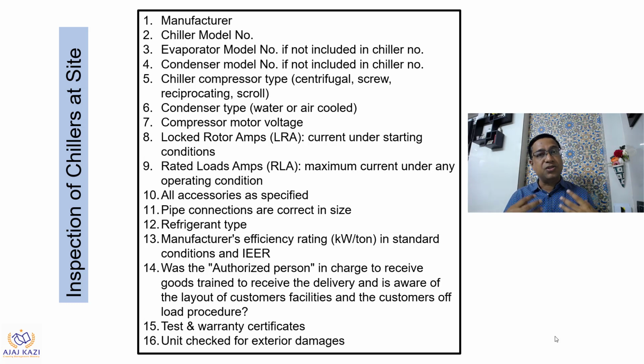Then the condenser type, whether it is air cooled or water cooled. What is the compressor motor voltage, and is it as per our approved submittal or not? What is the locked rotor amps, called LRA, again the current under starting conditions? And the rated load amps, the maximum current under operation of the chiller. That needs to be checked.